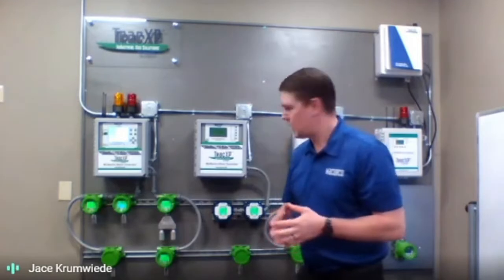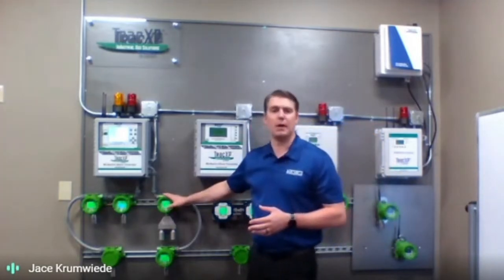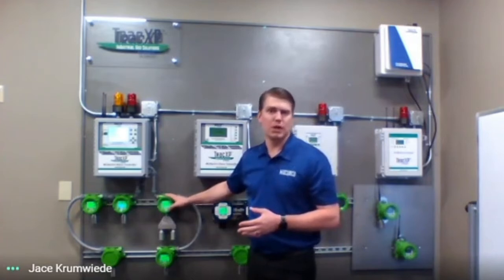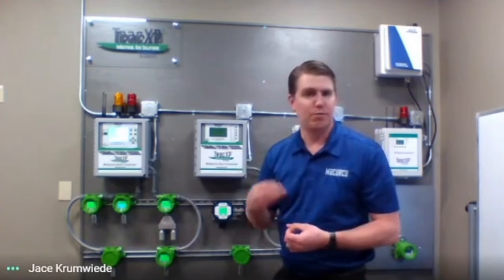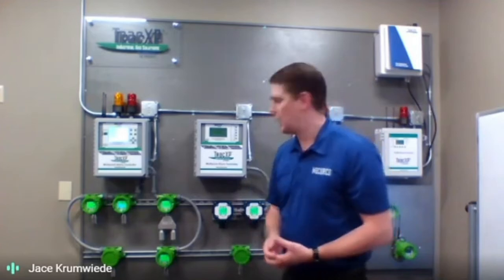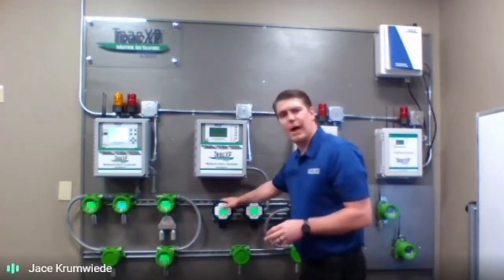You'll see a lot of the control panels, different inputs, anywhere from 2-channel, so 2 detectors, up to 64 detectors. So it's really about providing a specific solution that's going to meet your needs when you're talking about TraceXP. Different enclosures. What you'll see here, these green units, these are aluminum Class 1 Division 1 enclosures. So you'll have a wide variety of gas types. You'll have different outputs available. Whether that's Modbus TCP, Modbus RS-485, 4 to 20 milliamp analog outputs, and also onboard relays. We can accommodate those different options. So again, finding out what you need for your solution is how we're going to piecemeal that specific solution together.